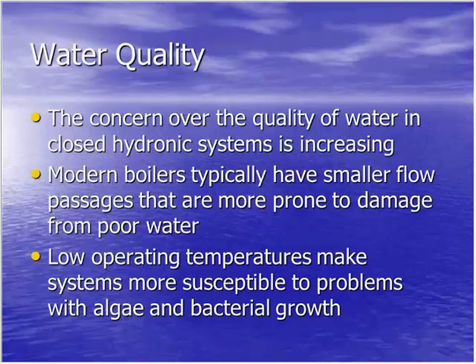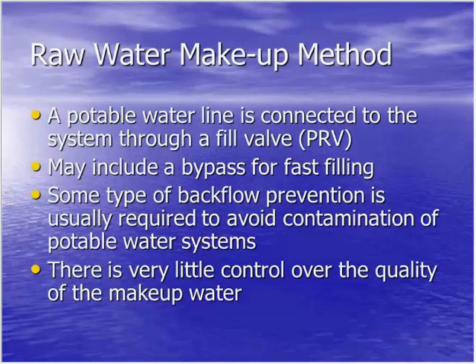The typical method of maintaining pressure, or maintaining that cold static fill pressure in closed loop systems, is what I call the raw water makeup method. Essentially, it's a potable water line that's connected to the system through a fill valve or pressure reducing valve. It may include a bypass for fast filling. And some type of backflow prevention is usually required to avoid contamination of potable water systems. That can be a double check backflow preventer, a reduced pressure zone, an RPZ backflow preventer, testable backflow preventers. And there's very little control over the quality of the makeup water. Essentially, what you're getting out of your domestic water supply is what's being introduced into your system.